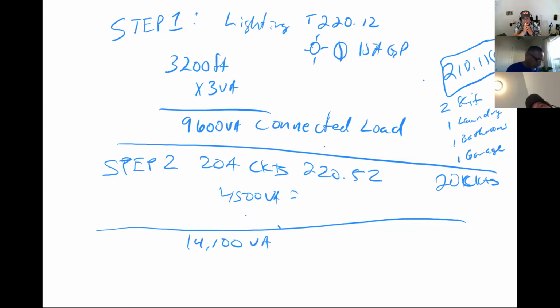Now, it's unlikely that the connected load would ever happen, so again we're going to look to diversify that because we know there'll be some lights that won't be on and some things that won't be plugged in. So if you look at the table on page 72, this is basically step 3, and step 3 is effectively our first derating step, and that is table 220.42 on the right-hand column of page 72.